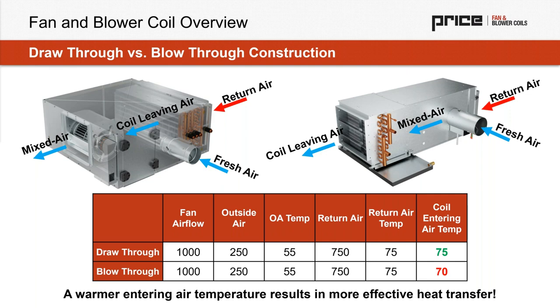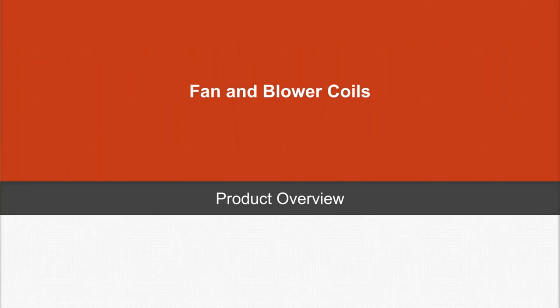So heating, we sometimes see blow-through products operate a little bit more efficiently, although heating tends to be less constrained and lower loads generally than we see on the cooling side. There's also options for a blow-through heating option with a draw-through cooling product on blower coils, although that is not something that we see on fan coils. So that's a little background, and now I want to talk more specifically about some product and application.